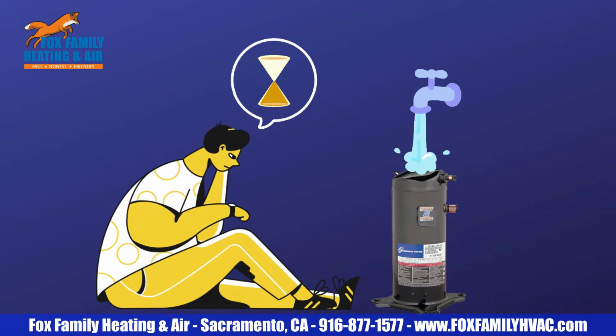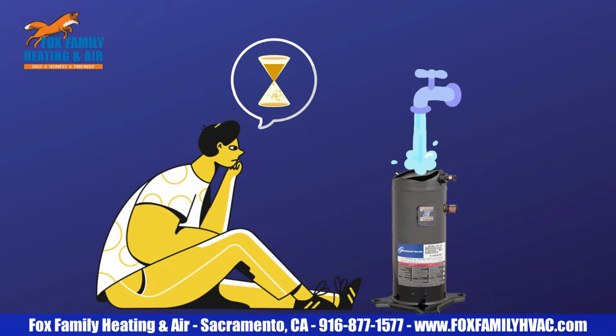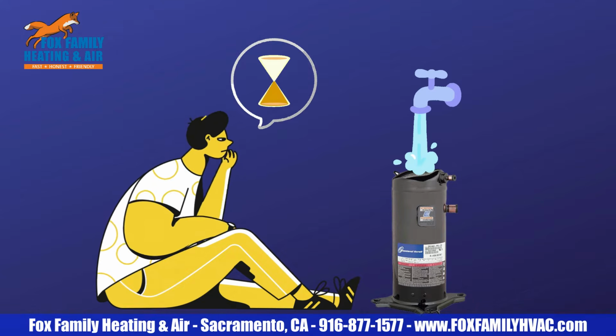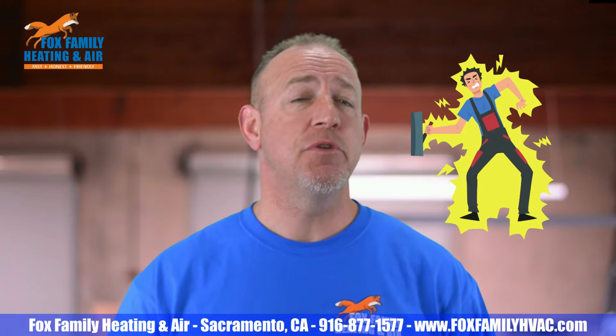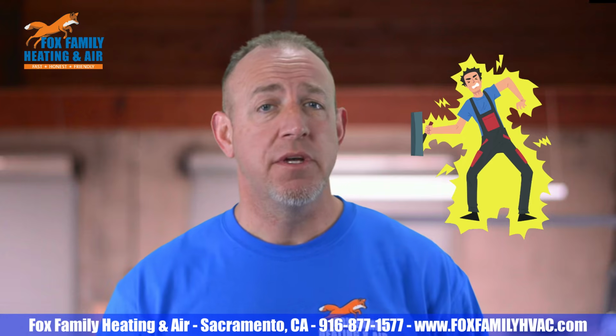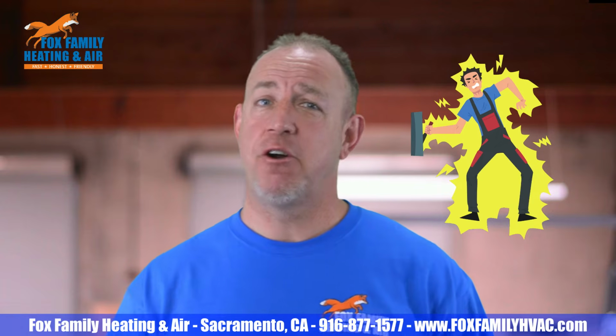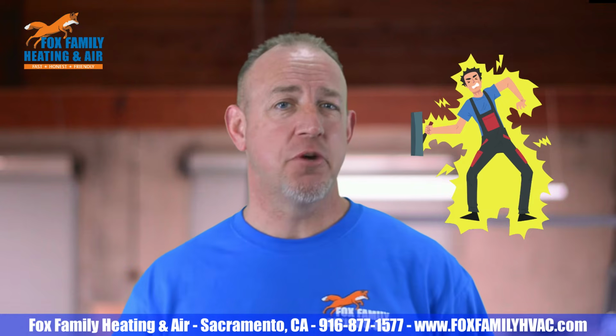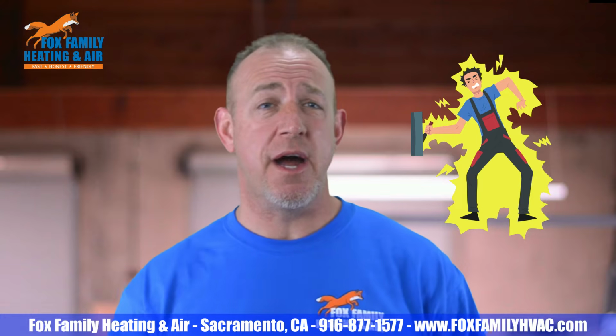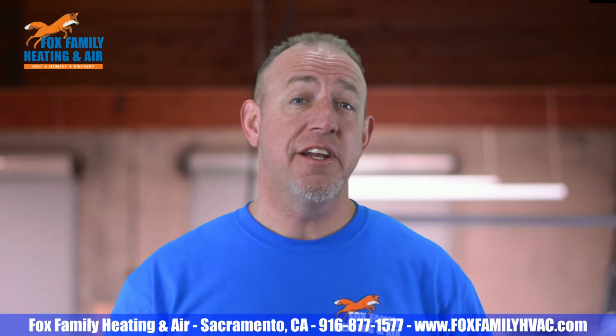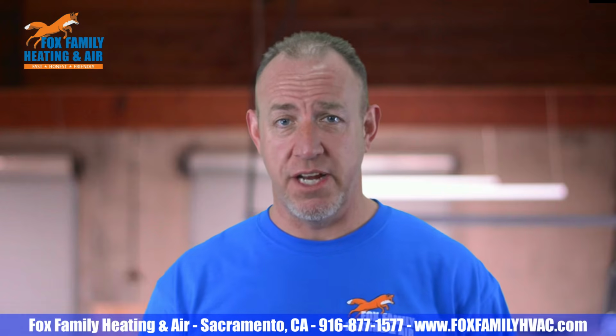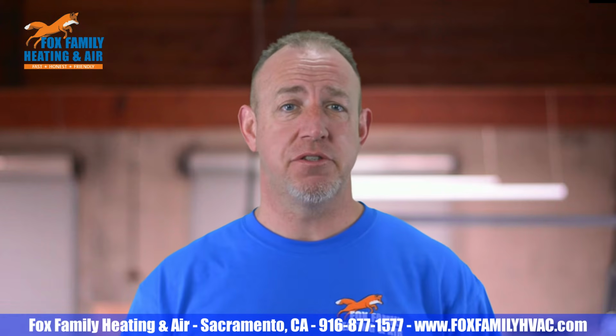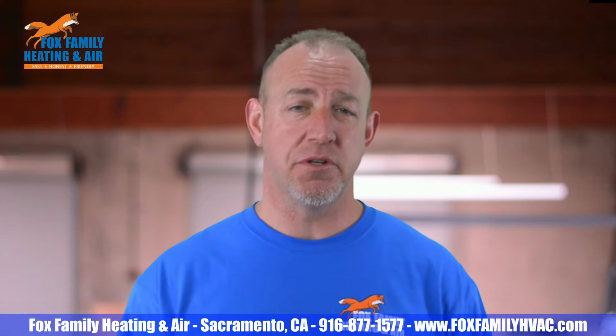It can take about 30 minutes of cooling before the internal switch closes and allows the voltage back to the common terminal. Be careful when you turn the unit back on later though. Standing water and high voltage aren't a good mix, so make sure your terminals are covered and exposed wire is waterproofed. You're going to need to find the reason why the compressor is overheating, but never start that compressor up without replacing the cover on the terminals.